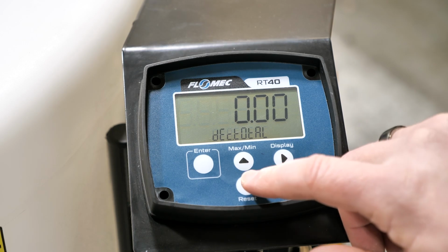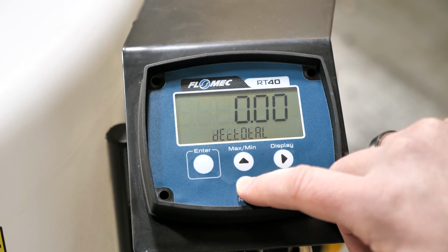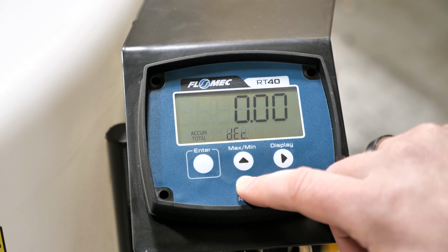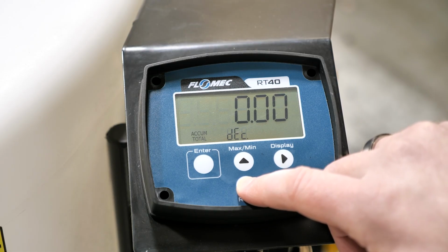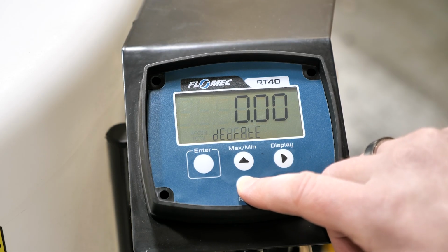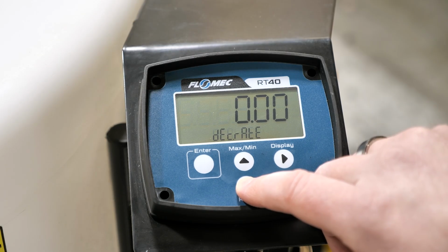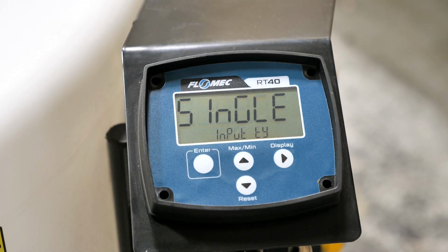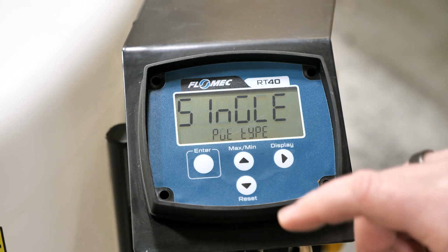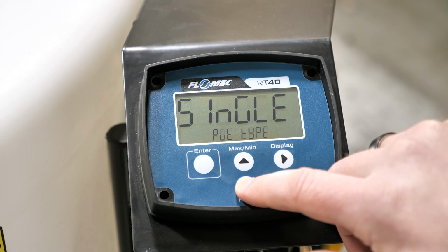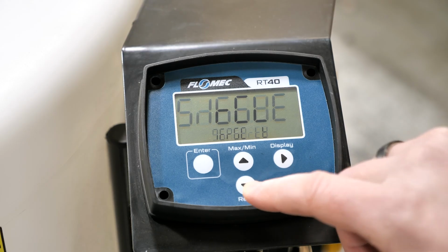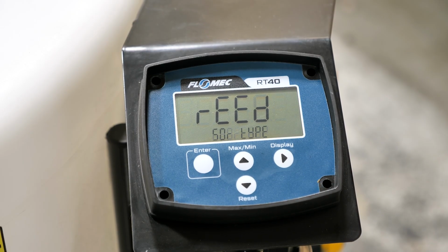This is a setting where you can change your decimals on your display. I leave those the default as well. Again, that's an accumulated decimal conversion as well. Another decimal thing that you can change. The next setting is your input type, which needs to be set as single. So that is correct as it is right now. The next setting is your sensor type, and it needs to be set up as a reed sensor type.